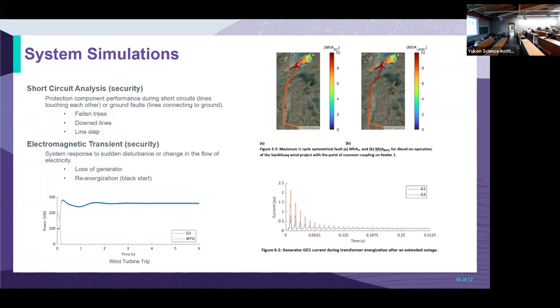The fourth simulation studies the effects of inrush current when we need to re-energize the large step-up transformers that connect to the solar plant or wind turbine, and to the thermal plant, the diesel generator. This is also a very short amount of time, since it stabilizes after about 1.3 seconds.